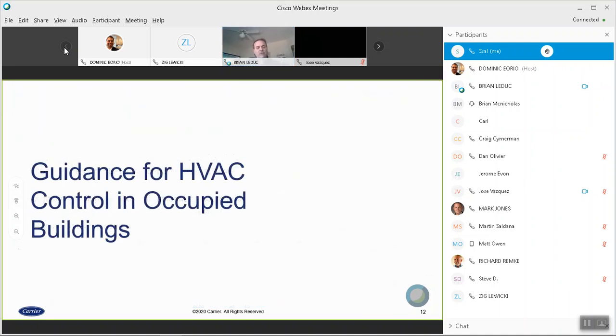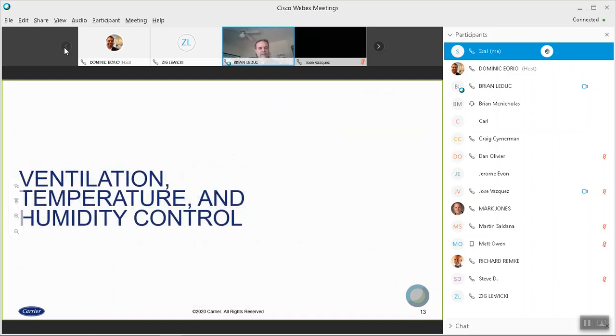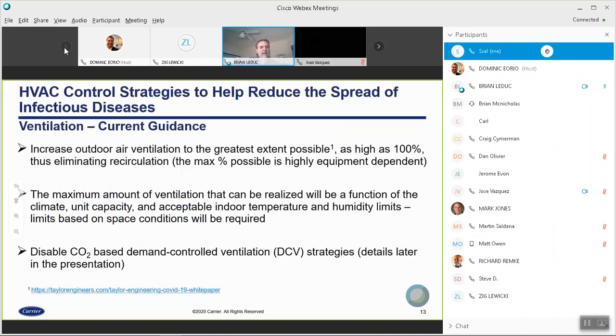Okay, so now we get into the real meat and potatoes, if you will. ASHRAE guidance for control in occupied buildings: ventilation, temperature, and humidity. Right off the bat, ASHRAE is recommending increasing outdoor air ventilation to the greatest extent possible, as high as 100%, thus eliminating recirculation.